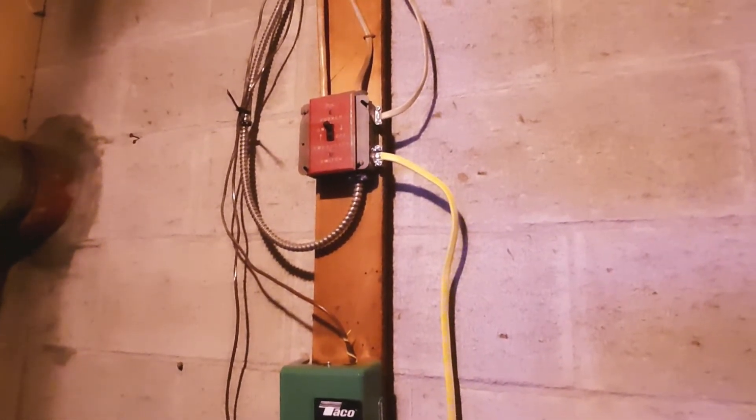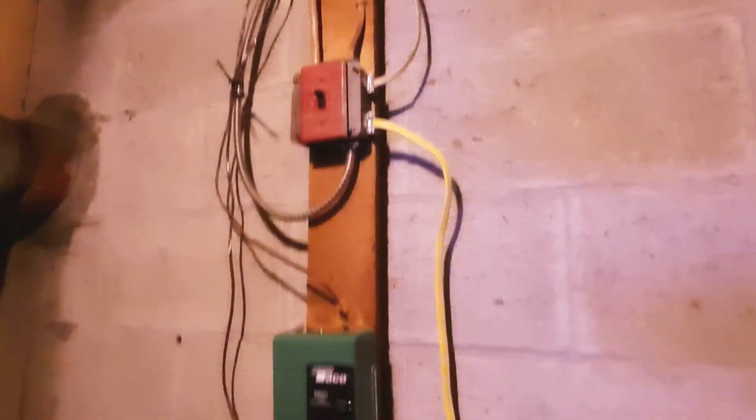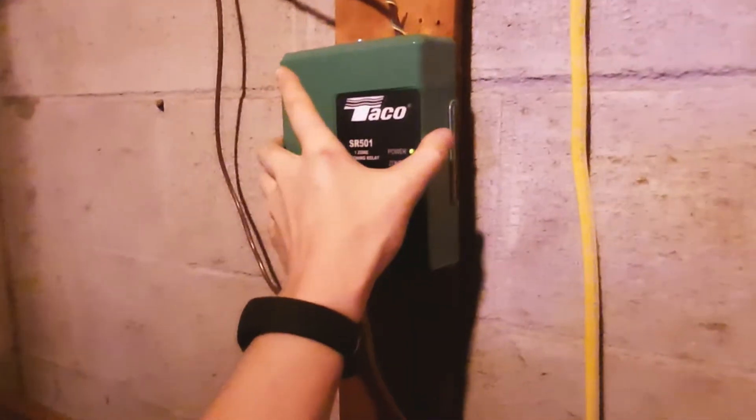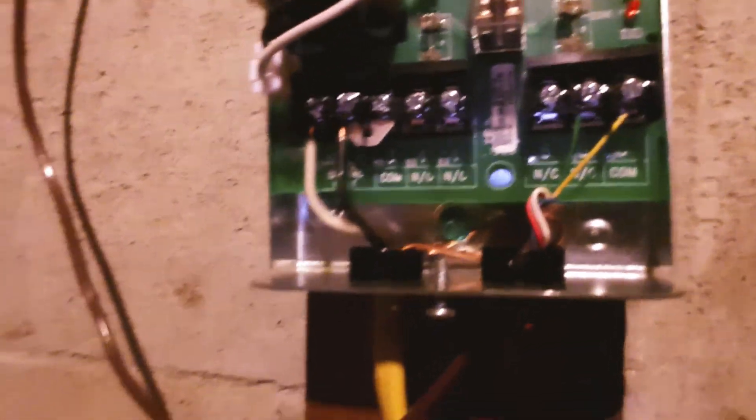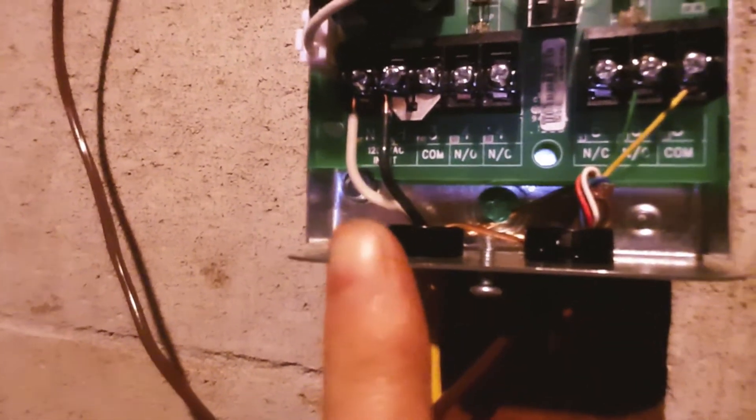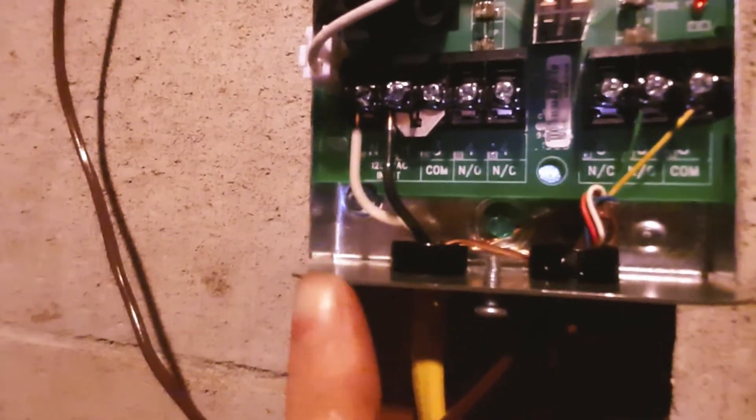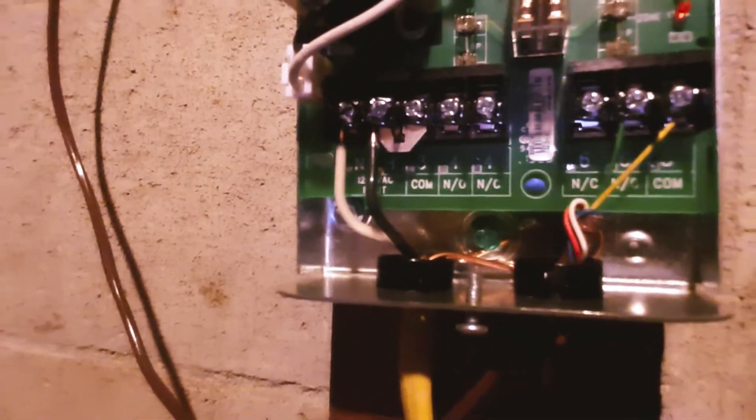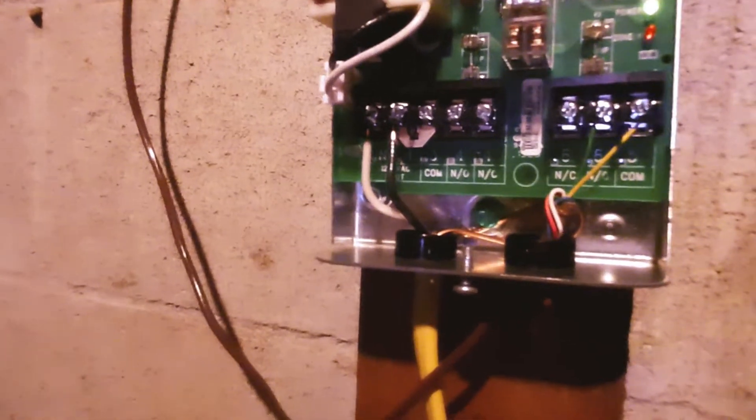And you can see here, I just tapped into the oil burner emergency switch because you're going to need 120 volts at the bottom of this switching relay, which you can see you've got neutral and hot for the 120 VAC input. And this is all in the instructions on the Taco switch.